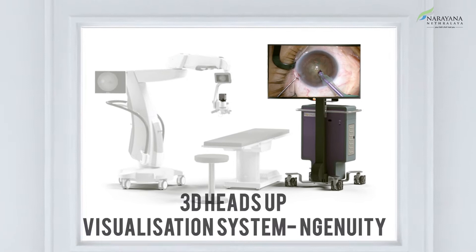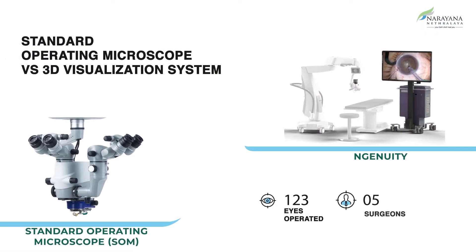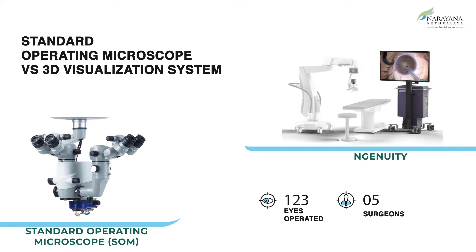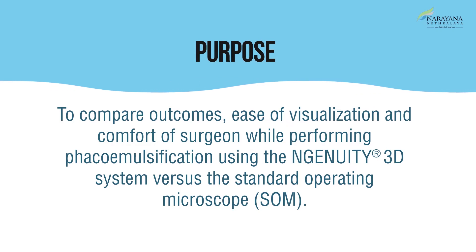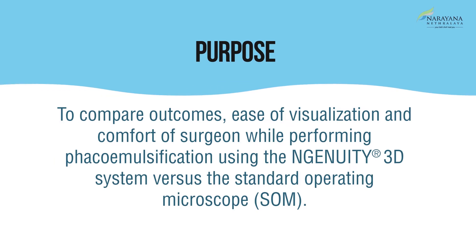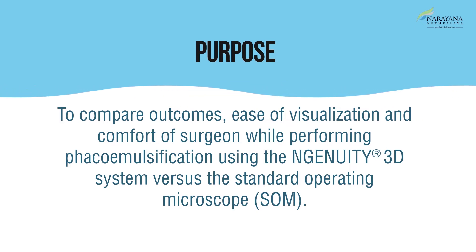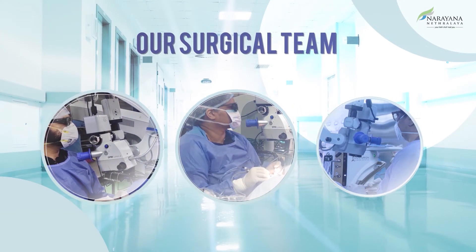We at our institute conducted a study aimed at finding significant differences, if any, between the standard operating microscope and the NGENUITY three-dimensional visualization system, using certain predetermined parameters. The study included 123 eyes operated for cataract. Our purpose was to compare outcomes, ease of visualization, and comfort of the surgeon while performing phacoemulsification using the NGENUITY 3D system versus the standard operating microscope. Our team involved five surgeons.